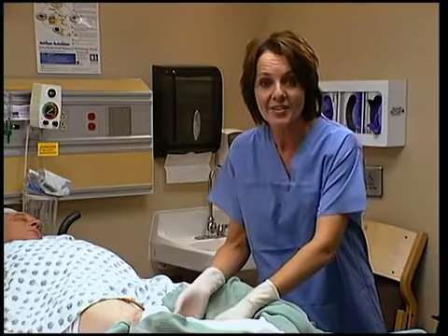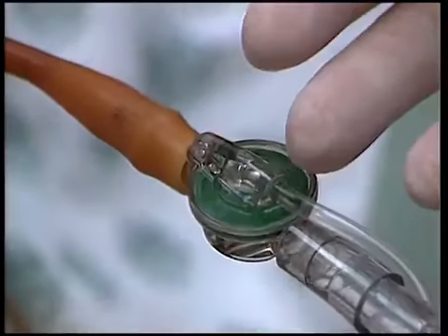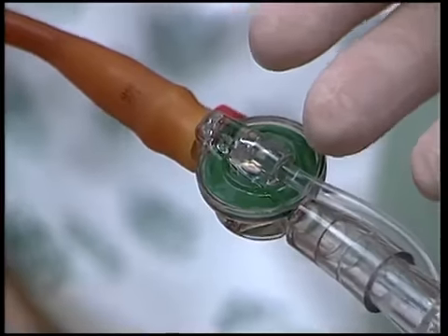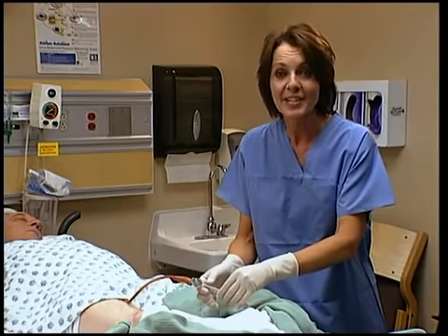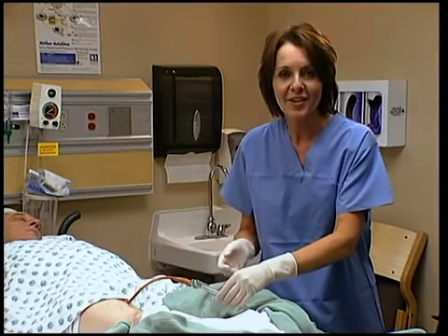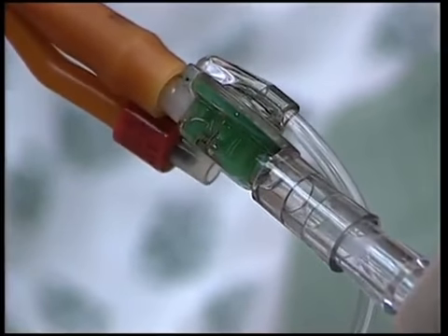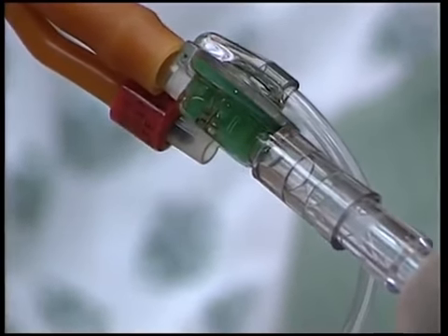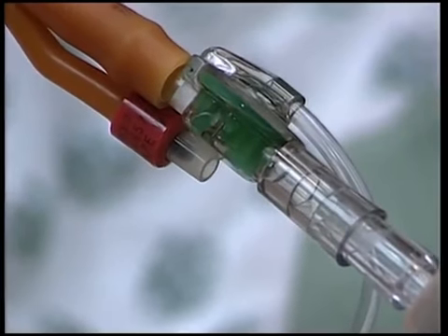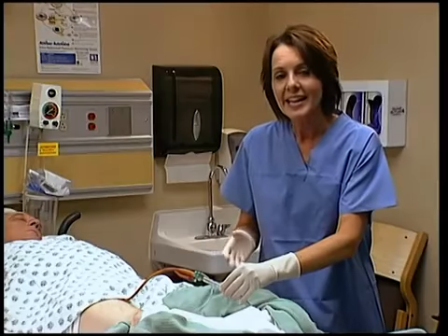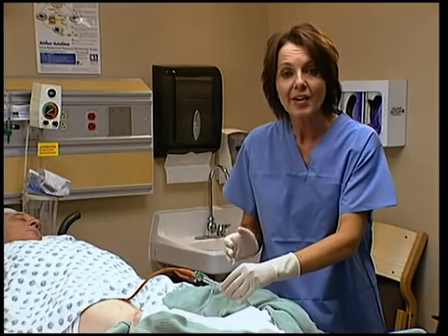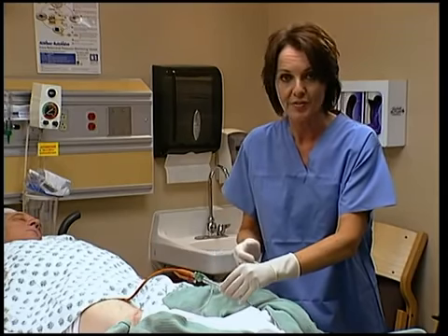The heart of the AbViser is a unique valve that connects directly between the urinary catheter and the drain tube. Once it is attached, the system never needs to be opened again, maintaining a sterile urinary drain system. When fluid is injected into the system, the diaphragm within the valve is automatically inflated, occluding the drain and directing fluid into the bladder. In this inflated position, you are able to accurately measure intra-abdominal pressure.